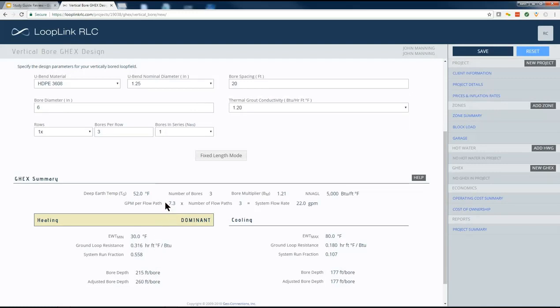Notice that I expressed a little bit of concern over the flow rate relative to the depth for the first pass at our design with 2 bores. But considering how shallow these bores are, I'm going to go ahead and go back now and let's go to our 2-bore option, spaced 20 feet on center with a 1.2 grout. Now notice those bores are less than 400 feet each for this entire 7-ton system.